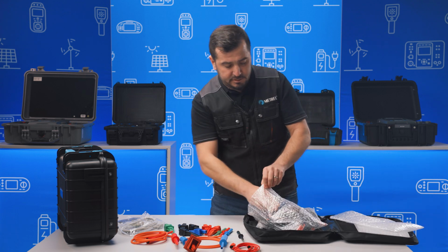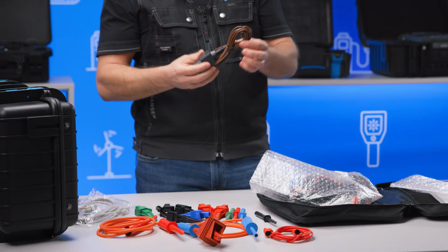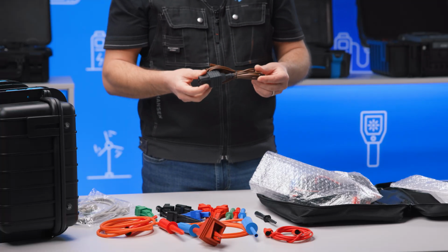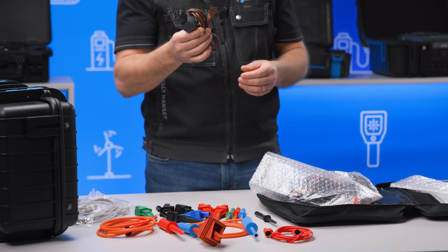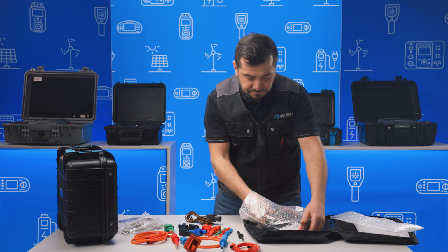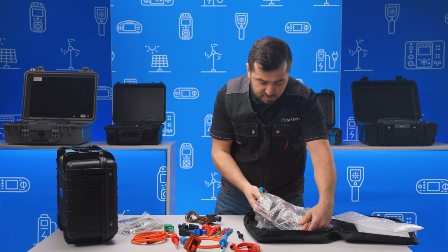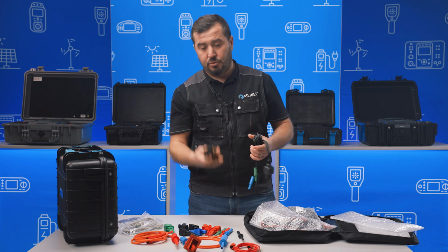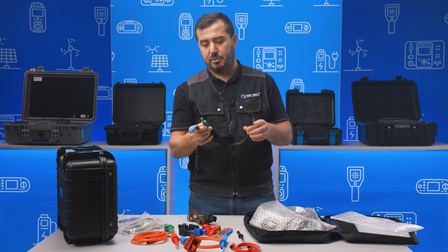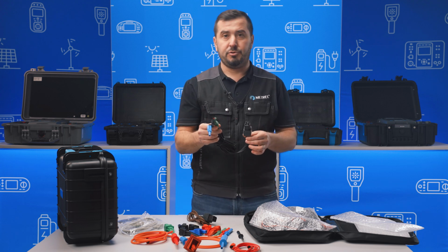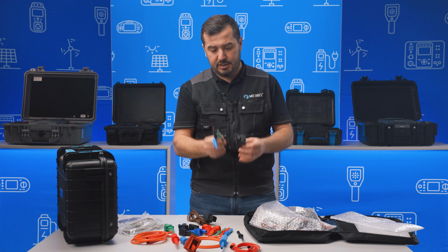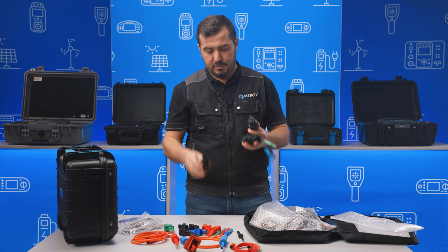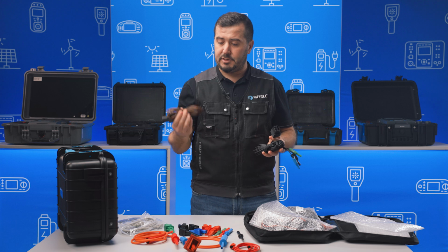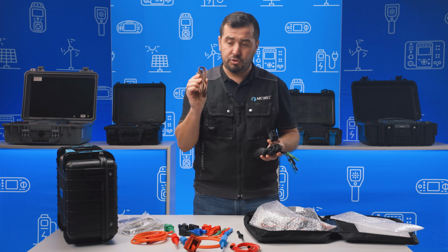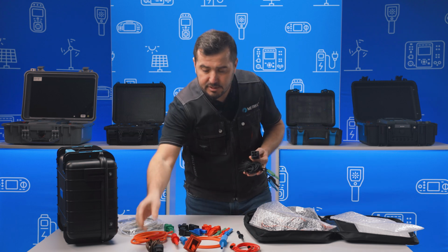Then inside the next bag, this here is the cable for testing residual voltages. This is very important to remember because the connection cable on this cable and the other cable, which is the universal three-wire test cable, are the same. But if you would like to test residual voltage, you should use this specially dedicated cable.